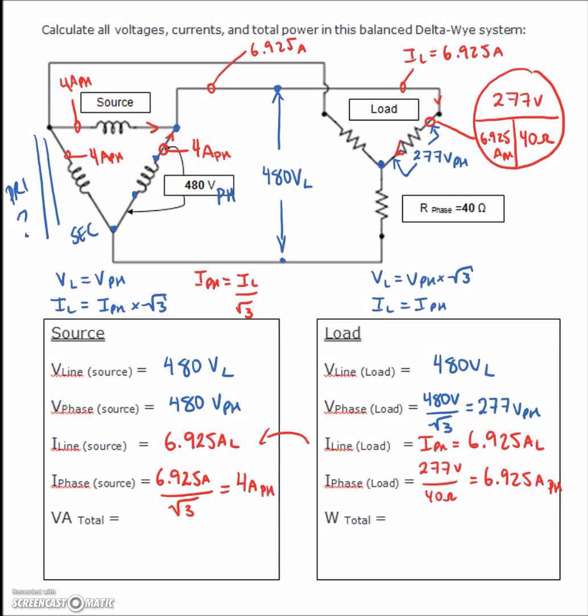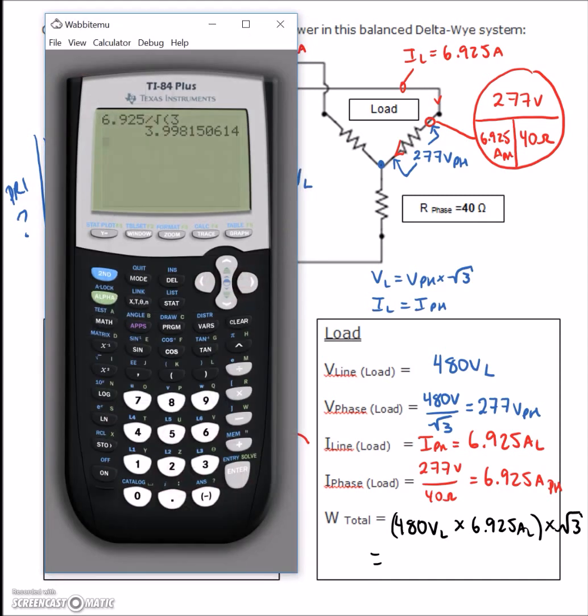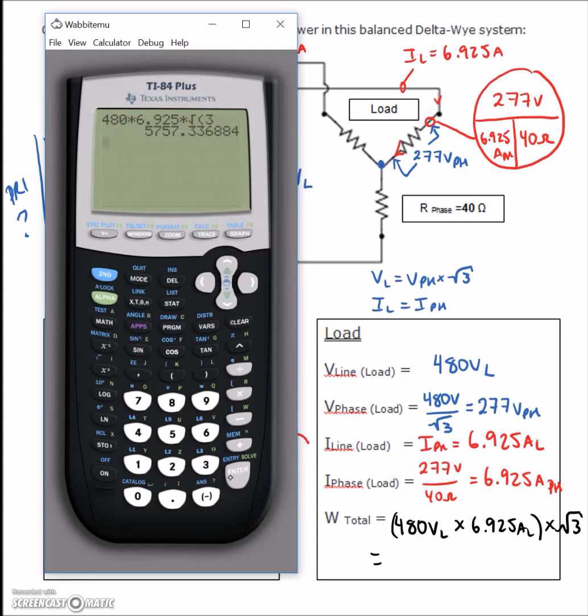Last, we find the power values. Total wattage = V_line × I_line × √3 = 480V × 6.925A × √3, which gives us 5,757.34W.